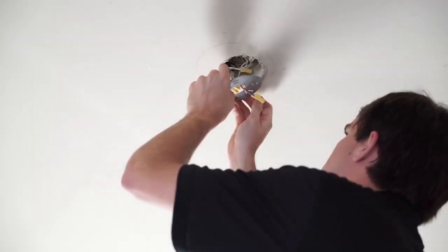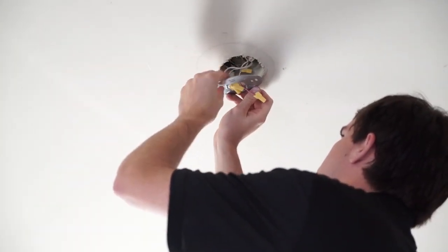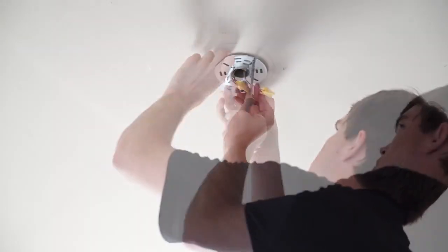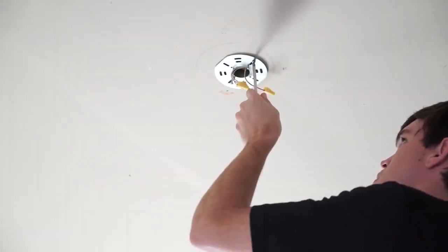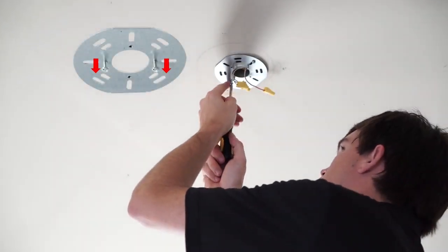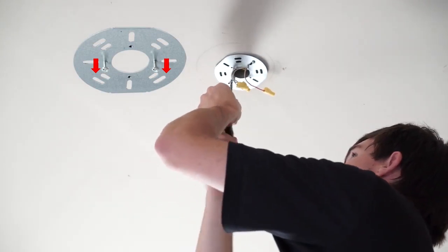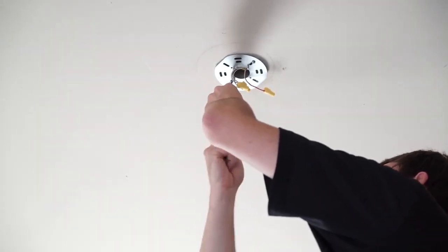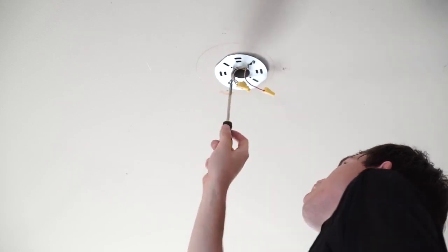For direct wire installation, position the mounting plate over the junction box and feed the supply wires through the center holes. Be sure the screws that are already installed in the mounting plate are facing downward and are positioned to the correct fixture orientation. Secure the mounting plate using the 1.5-inch screws.